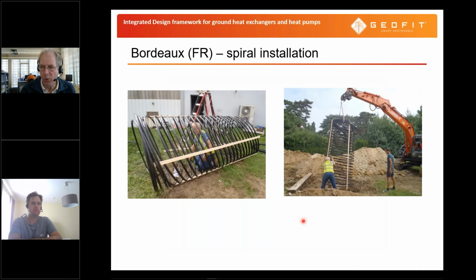And then just to go on, the other demo site in France, in Bordeaux, where we've installed an earth basket type heat exchanger. Actually, 2 earth baskets have been installed here with an additional vertical borehole heat exchanger, because although sufficient space was available, there was underground infrastructure that prevented installing more earth baskets.